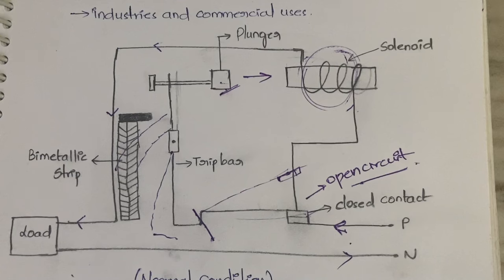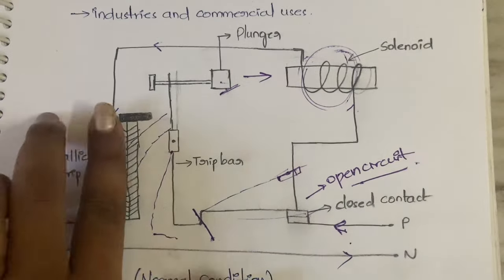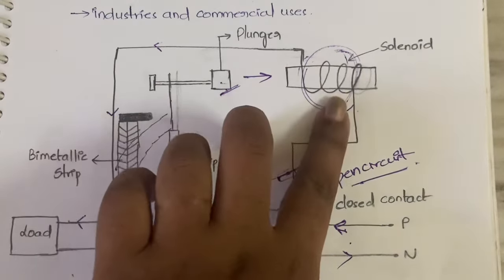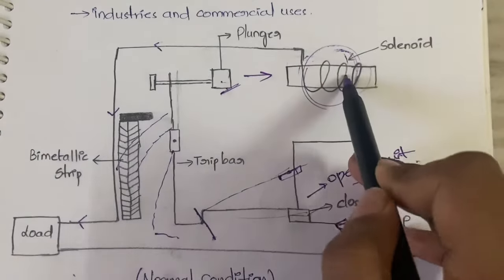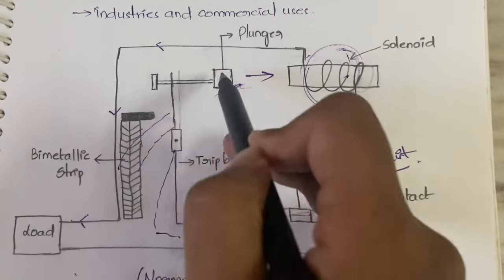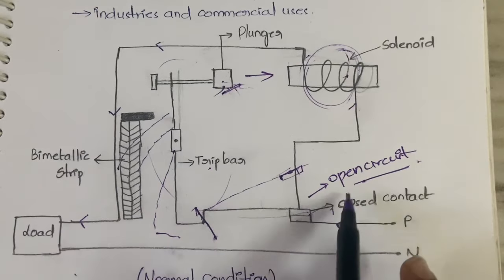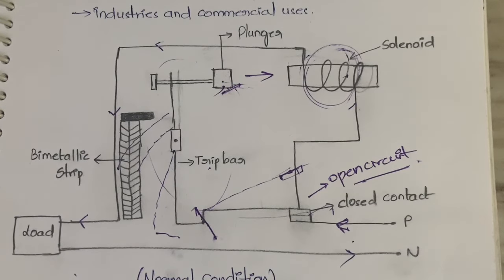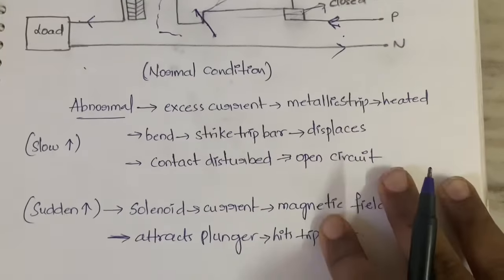The trip bar displaces again, the connection breaks, and the circuit becomes open — the same outcome as before. The difference is: in the case of a slow current increase, the bimetallic strip heats up, bends, and hits the trip bar. In the case of a sudden increase, the magnetic field attracts the plunger, which hits the trip bar, and the result is an open circuit.